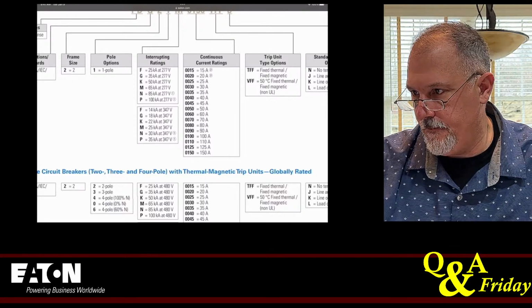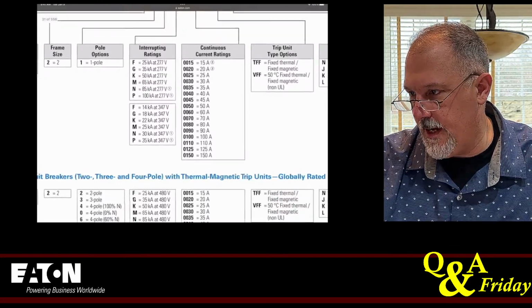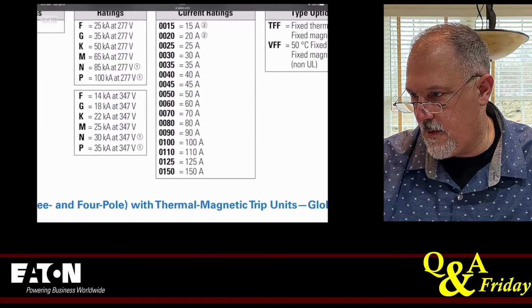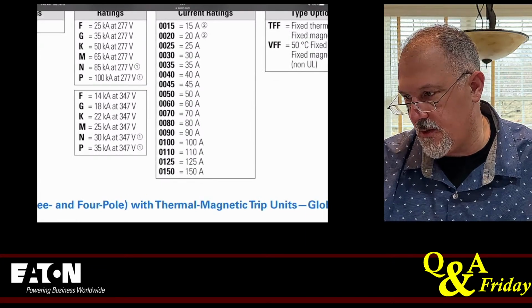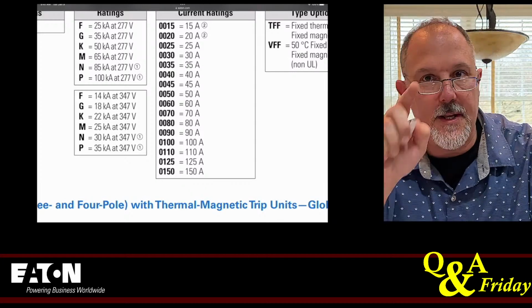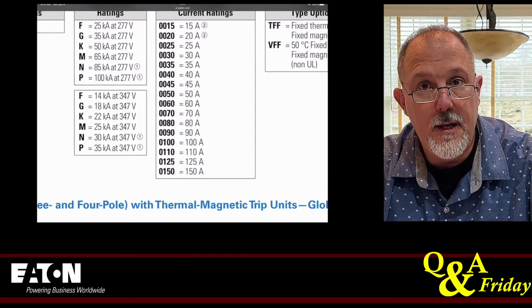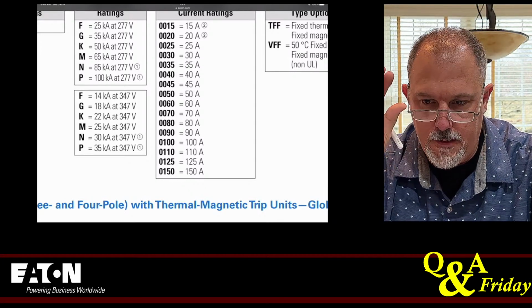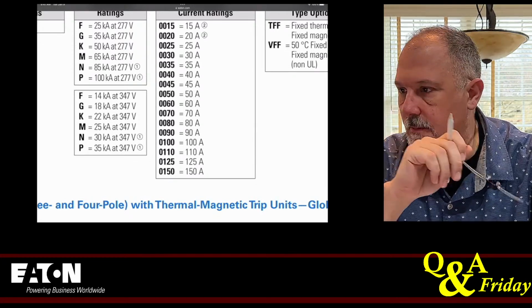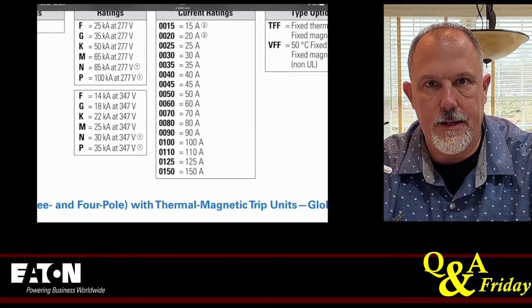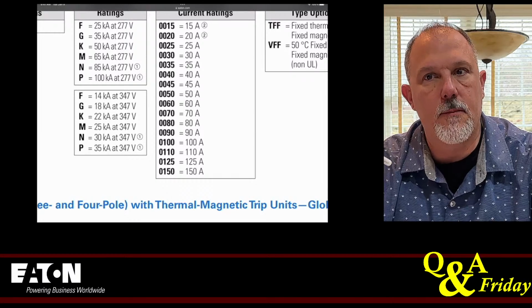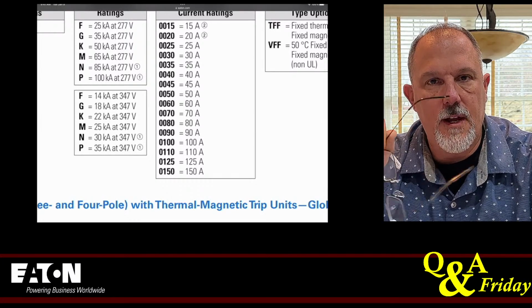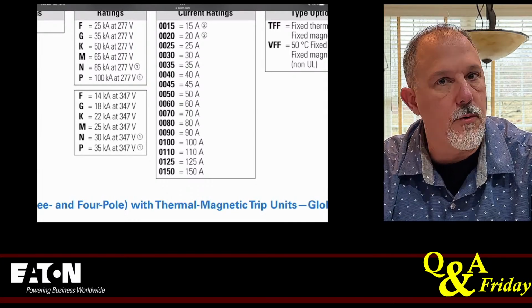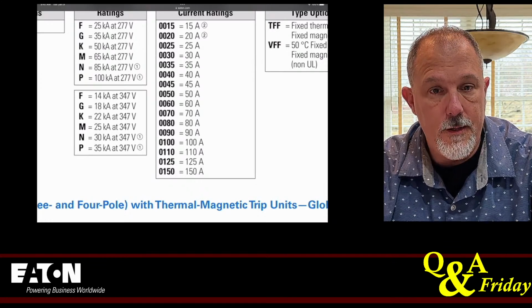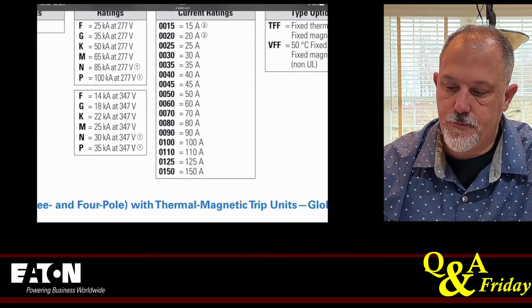F frame. Continuous current ratings: 125, 110. So 125 amp breaker. I could put that, and it depends on the panel board that I have upstream. I covered that, I think it was last week or this week sometime. It's important to recognize that when you're selecting an overcurrent protective device, you've got to think about what is the panel board or switch board that you're going to put it in. You just can't pick any circuit breaker.